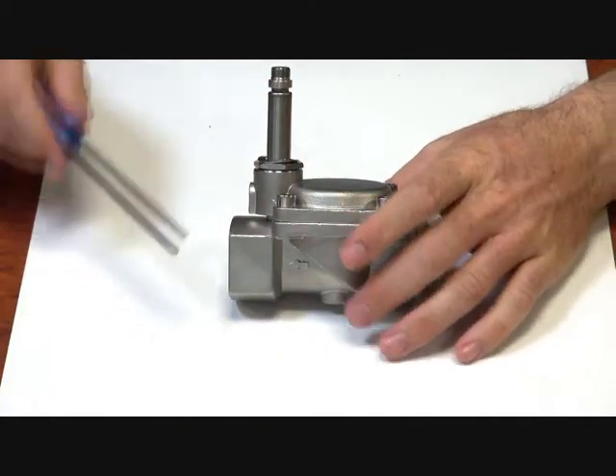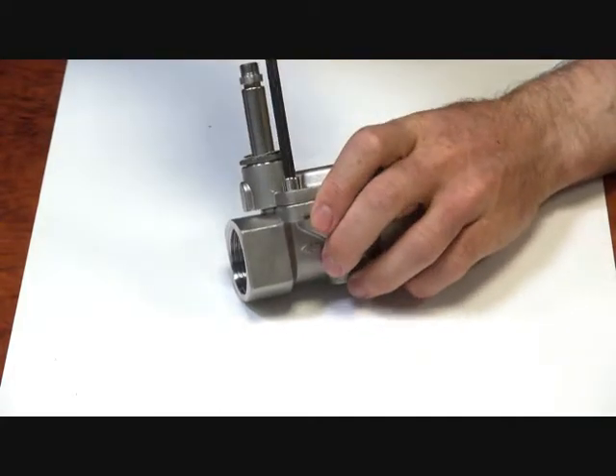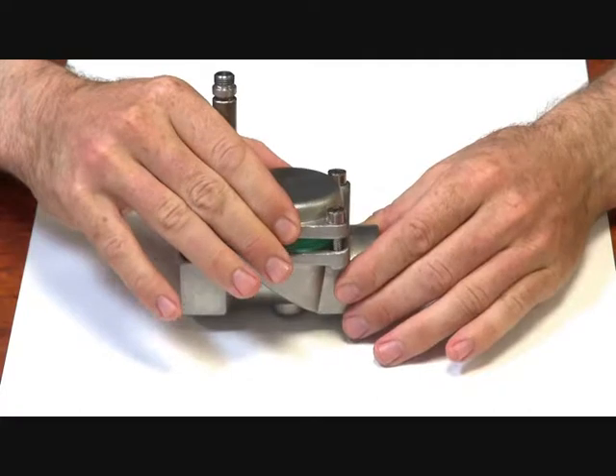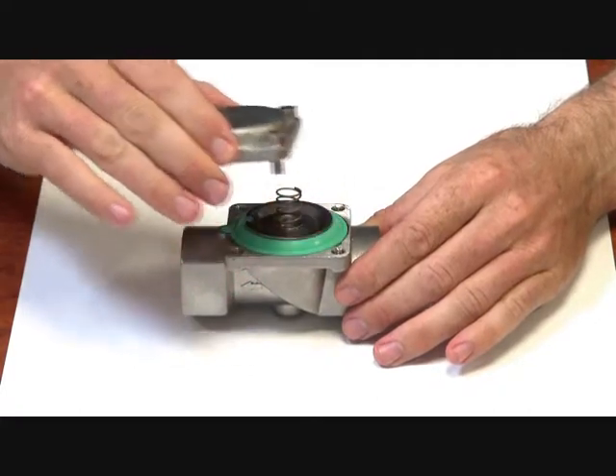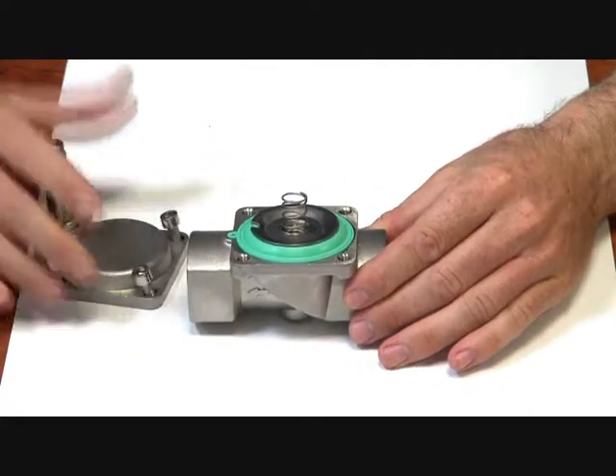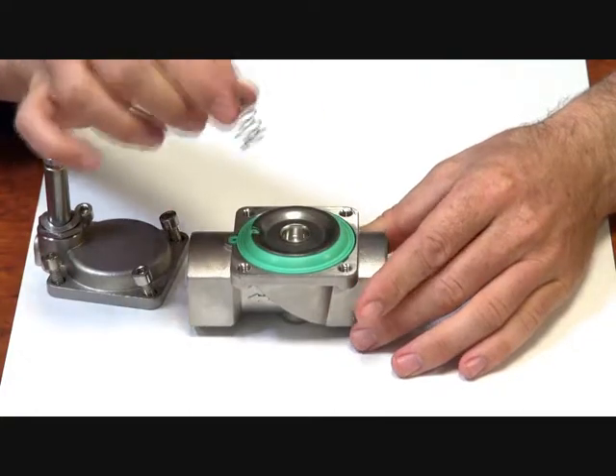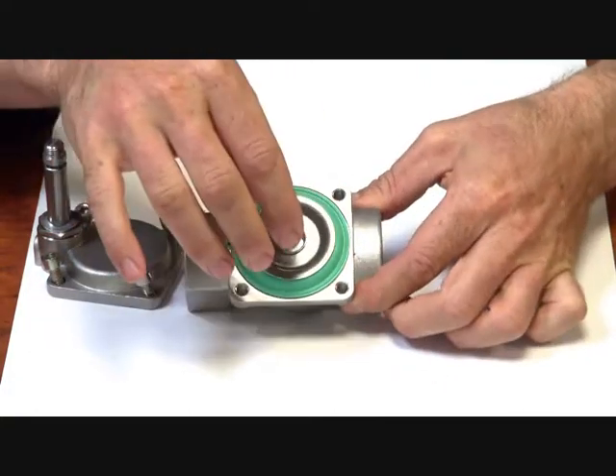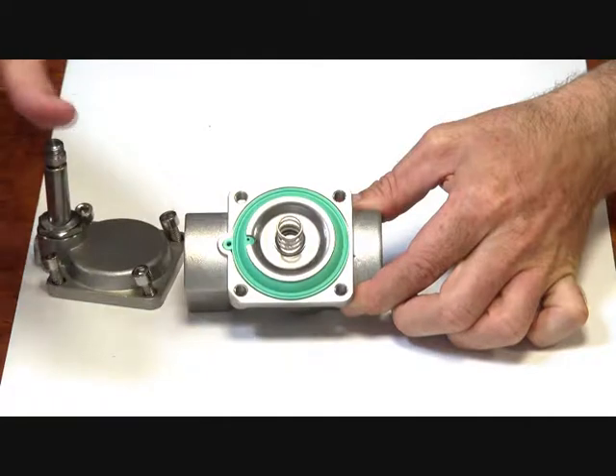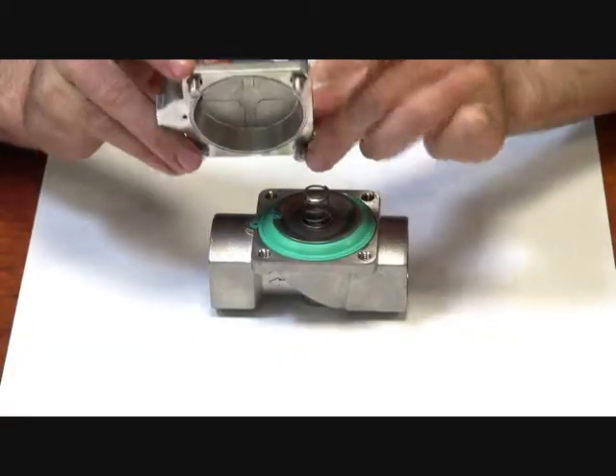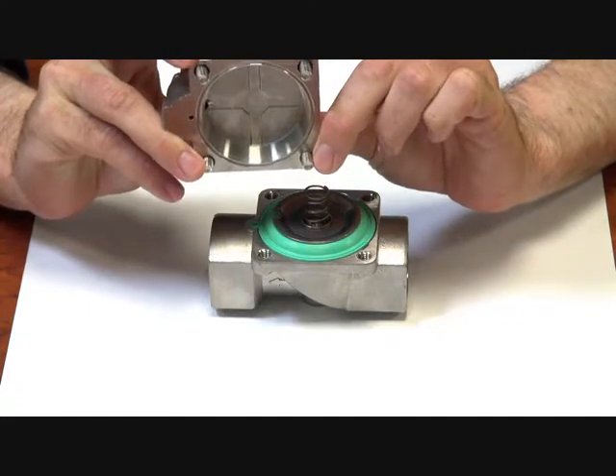So to take the body of the valve apart, I'm just going to loosen these four bolts off. So as we lift the top off this valve, you'll see underneath is a spring. Now this spring sits in a little seat there in the top of the diaphragm, and it pushes against the underside of this valve.